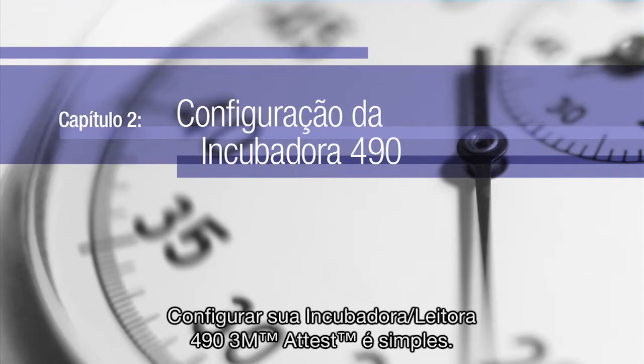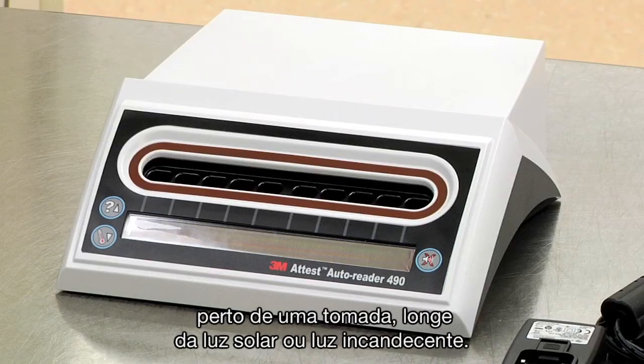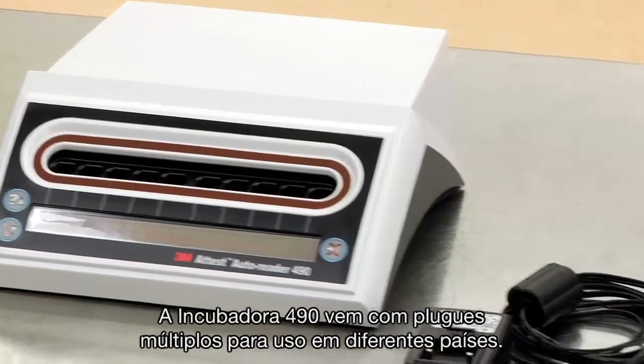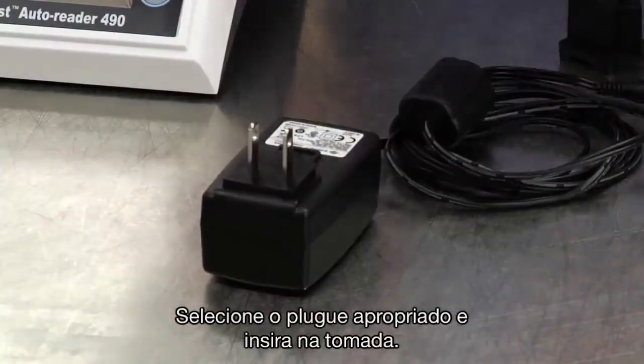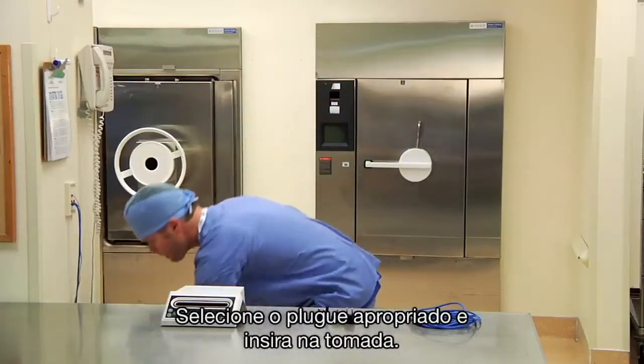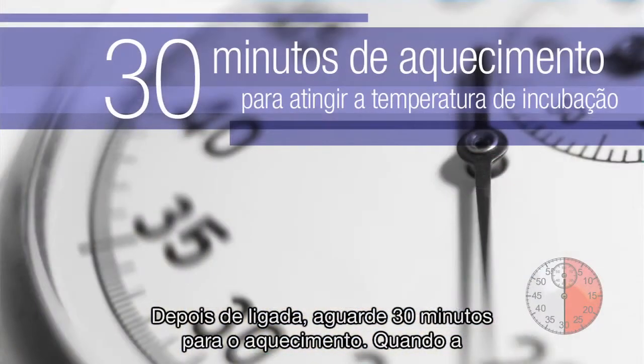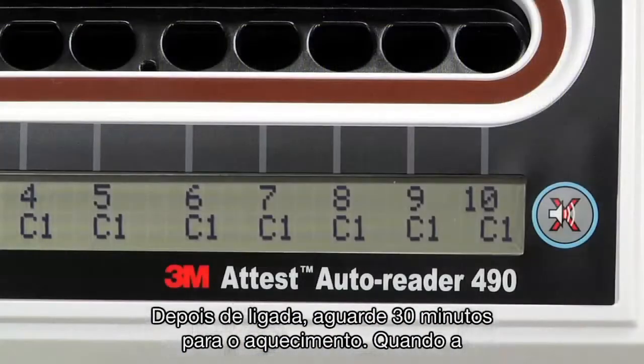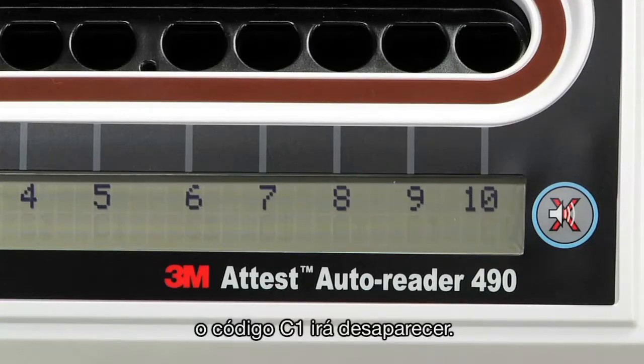Setting up and configuring your 3M Attest Auto-reader 490 is simple. Place it on a firm level surface near an outlet, away from sunlight and incandescent light. The Attest Auto-reader 490 comes with multiple power plugs for use in different countries. Select the plug appropriate for your country and insert it into an AC grounded outlet. If you plan to use the Attest Web App, connect the supplied Ethernet cable to an Ethernet jack. Once plugged in, allow it to warm up for 30 minutes. When proper incubation temperature is reached and the unit is ready to use, the C1 caution code will disappear.